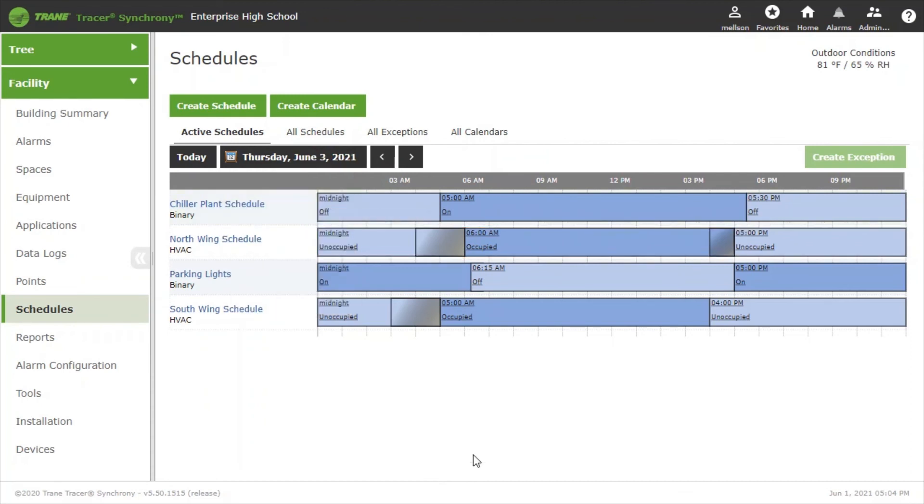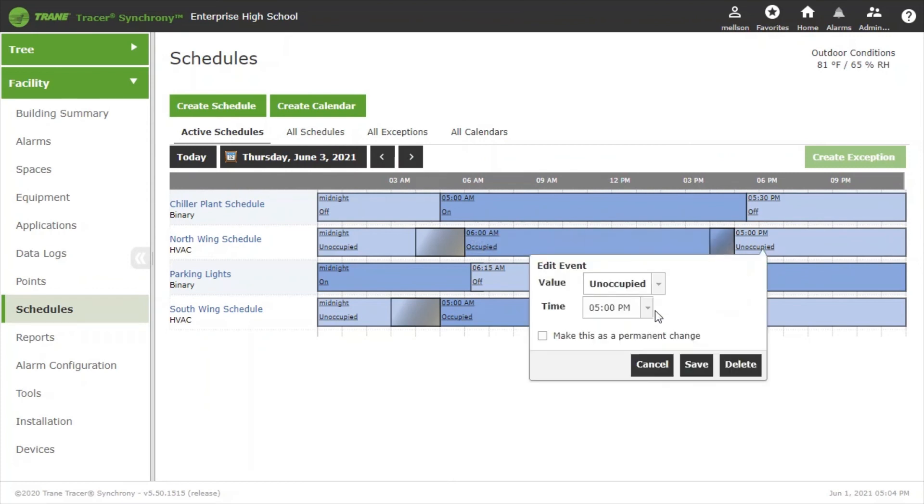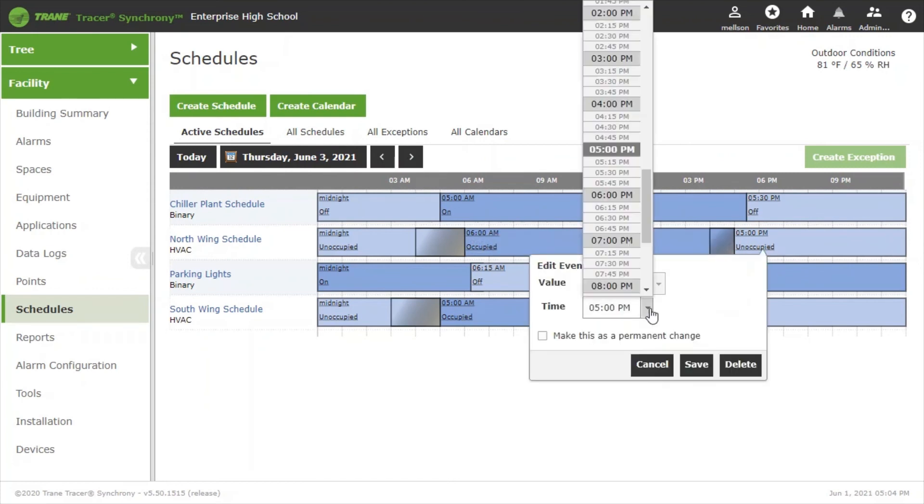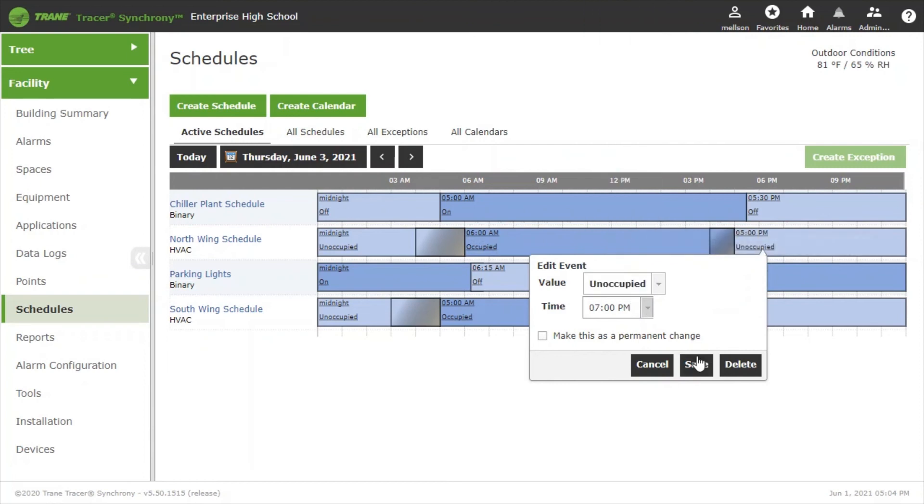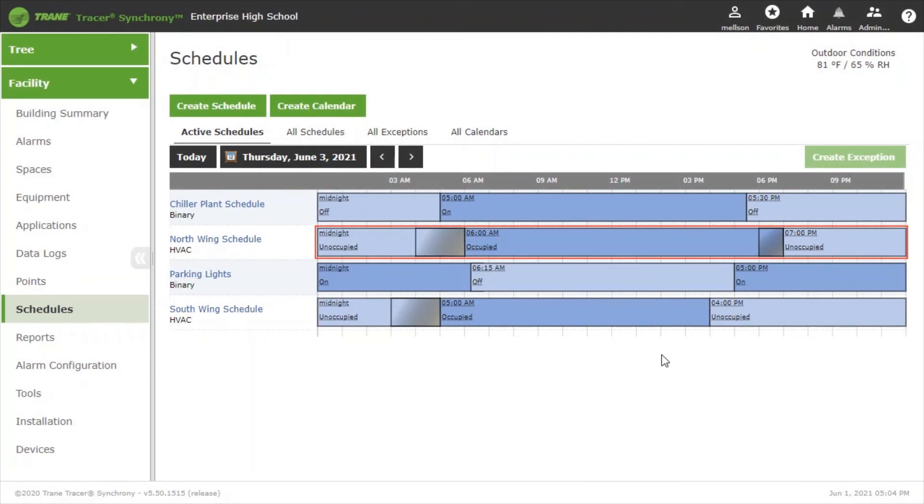You can see Thursday is still using the normal schedule of 6 a.m. to 5 p.m. Again we just click on the 5 p.m. unoccupied event, change the 5 p.m. to 7 p.m., and hit Save and we've made a one-time change to that schedule on Thursday June 3rd.